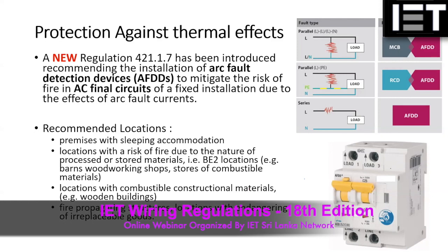And another part to that question, are AFDDs mandatory for healthcare premises? Healthcare is not listed here, because what you have to look at is whether there is a fire risk, a fire propagation risk within the premises due to arc flash. If so, only then can you go for it. Otherwise, normally in healthcare, even for the operation theaters, most of the locations are designed as IT systems where you don't want to disturb the electricity supply. But if you have a particular risk of arc flashes and the propagation of fire, then you can install it, but that will increase the risk of nuisance tripping.